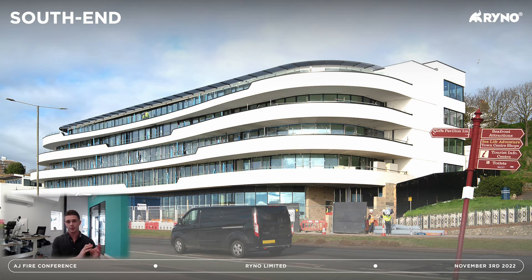When we're talking about balconies that is very different to a roof terrace. An interesting scheme in Southend, right down on the seafront - a very nice project and we're looking at the roof terrace in particular. Roof terraces, as they form part of the roof, have to comply with Part 5 of EN 13501, which is for the roofing classification - looking at fire resistance and fire penetration through the overall roof deck into the building itself. That fire classification is B Roof T4, which is looking not so much at the level of combustibility but at that penetration through the roof build-up into the compartments below.